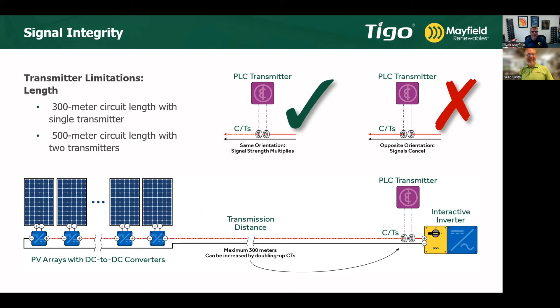More on signal integrity - we've talked about this. Again, Tigo specific: 10 conductors per transmitter, only on a single side. If you stuff it full, get more than 10 conductors inside that CT, you're creating a bundle, and the inside conductors of that bundle can't receive the signal. It's just not strong enough to penetrate through all of those conductors and get to the core of that bundle, and expect those to be able to carry the signal out.